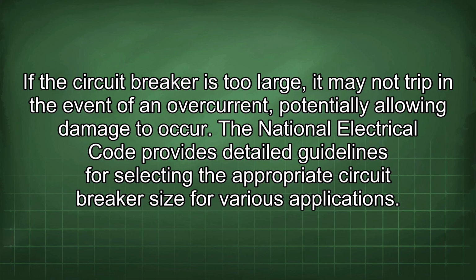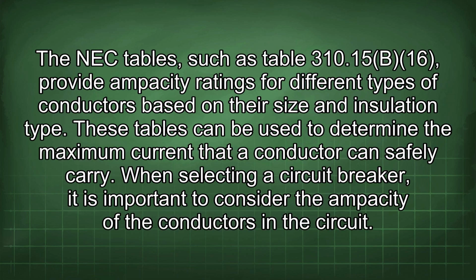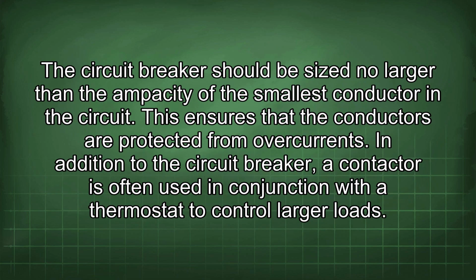to occur. The National Electrical Code provides detailed guidelines for selecting the appropriate circuit breaker size for various applications. The NEC tables, such as Table 310.15(B)(16), provide ampacity ratings for different types of conductors based on their size and insulation type. These tables can be used to determine the maximum current that a conductor can safely carry. When selecting a circuit breaker, it is important to consider the ampacity of the conductors in the circuit. The circuit breaker should be sized no larger than the ampacity of the smallest conductor in the circuit. This ensures that the conductors are protected from overcurrents.